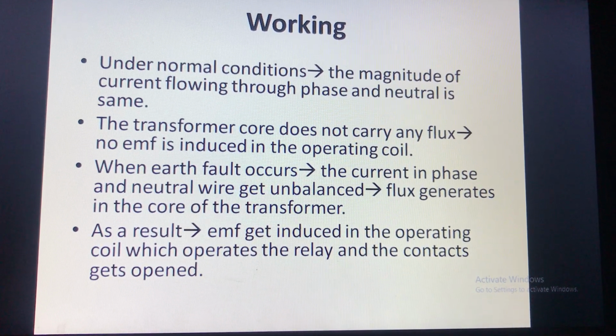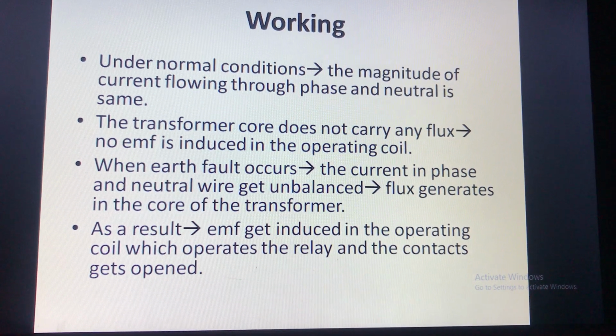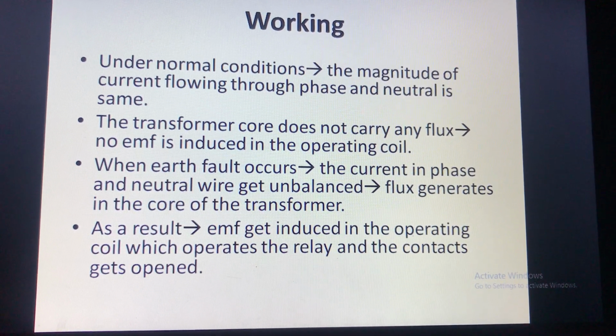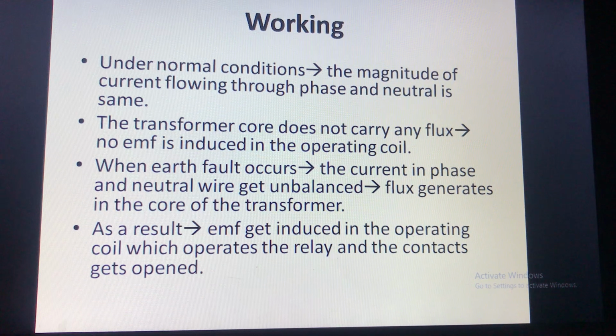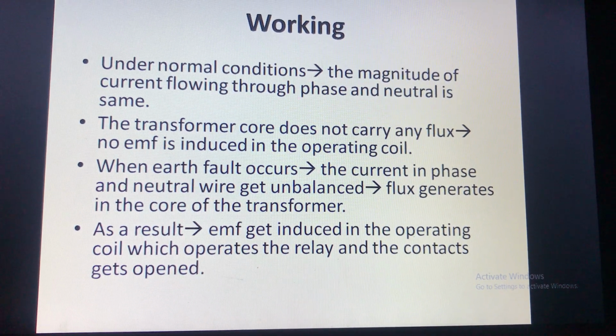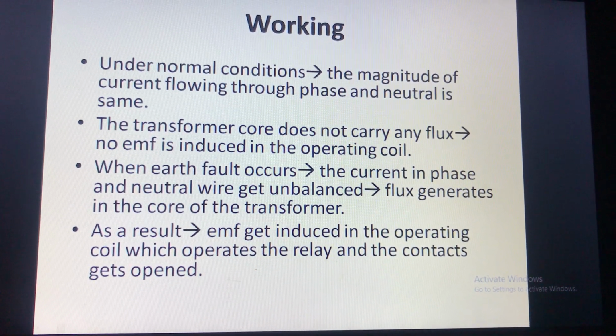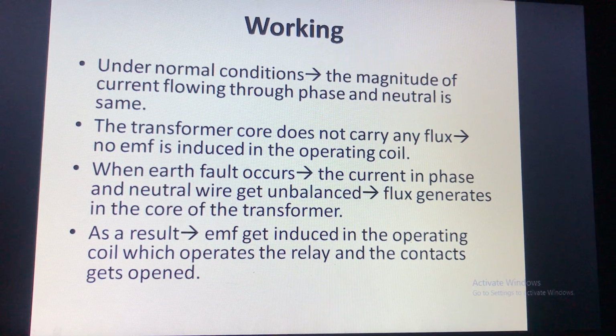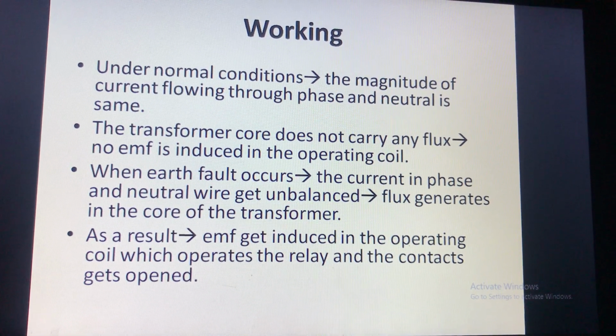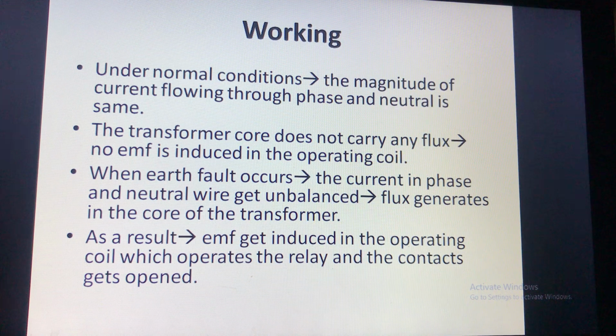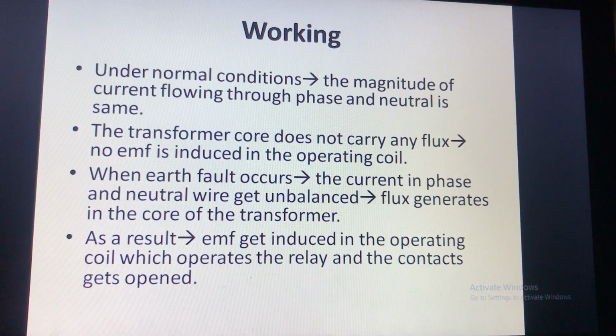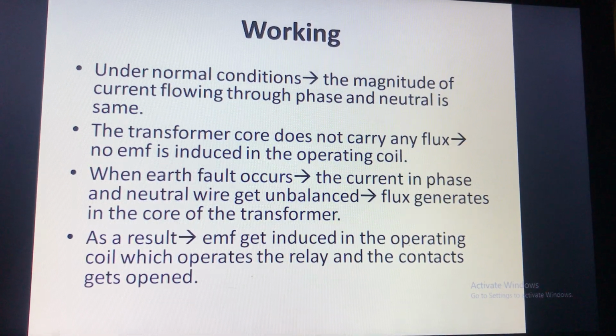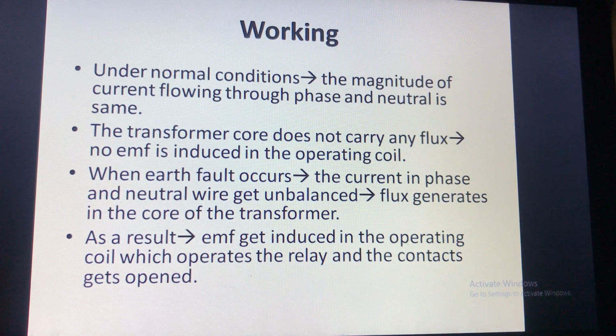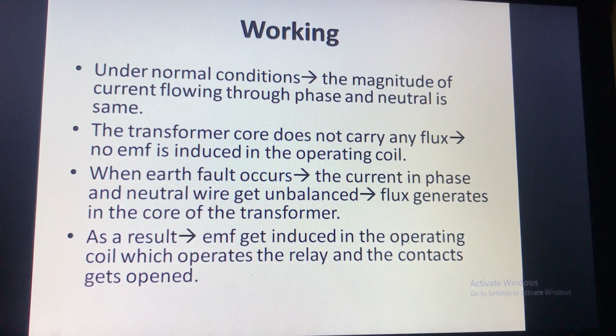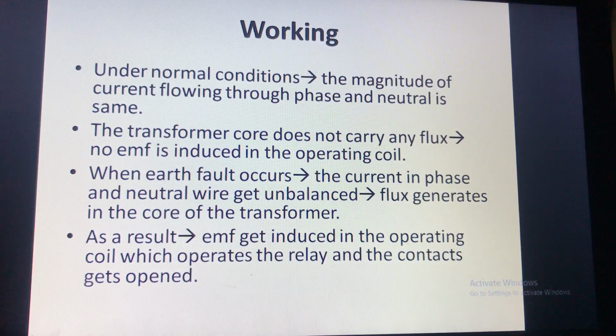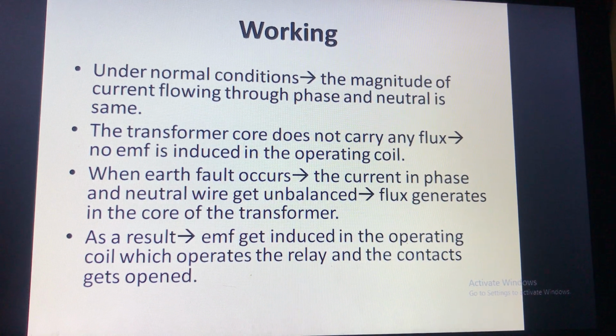When there is an earth fault or there is a leakage current, then this current will get imbalanced. Then the current in phase and neutral wire will not remain the same. Therefore, this change in current will lead to flux generation in the core of the transformer. As a result of this, EMF will get induced in the operating coil, which will further operate the relay and the contacts will get open.